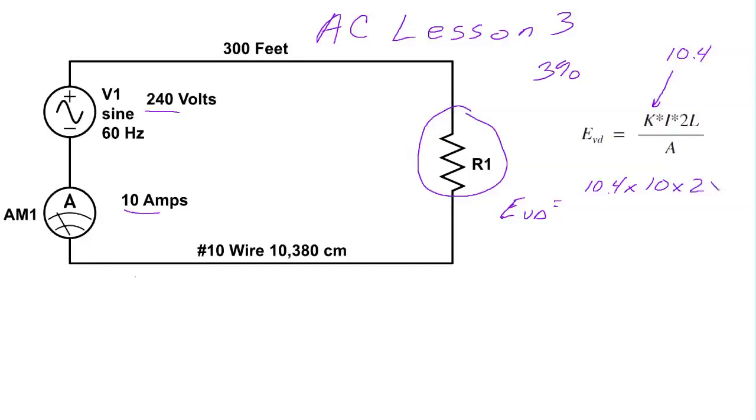We need to multiply by 2 because the load is 300 feet away, but that's just the length of one wire. So we need to multiply by 2 to get the length of both wires. So 2 times 300. We're going to put all that over 10,380, which is the circular mil area of number 10 wire.